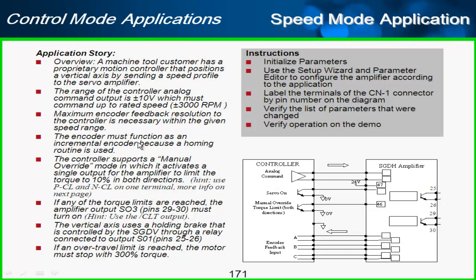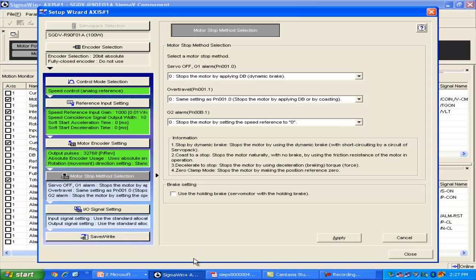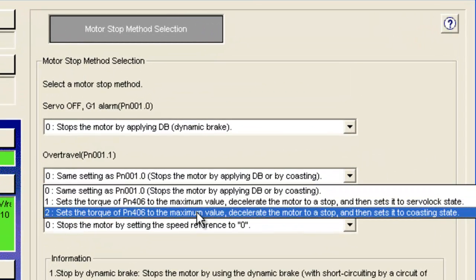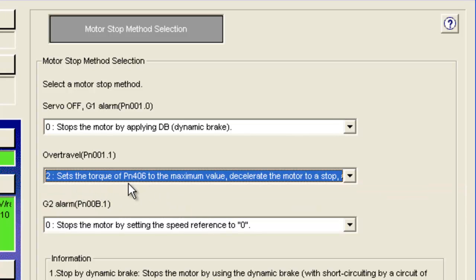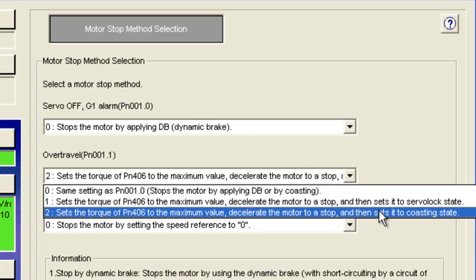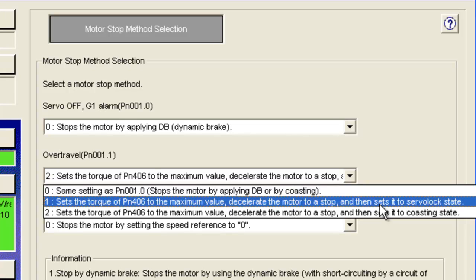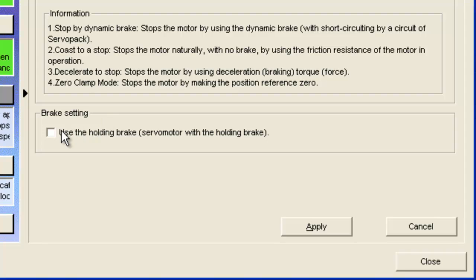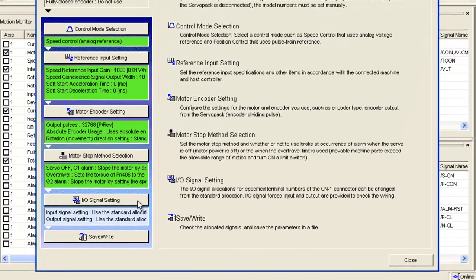Onto motor stop: the application calls for the motor to stop with 300% torque when it hits an over travel. So in the over travel stop mode I set it to stop with the torque of parameter PN406, decelerate the motor to stop, and then use servo lock state — leaving the servo enabled at the end. I'll have to go manually to PN406 later. This is also a vertical axis, so I'll check the brake motor settings box and hit apply.